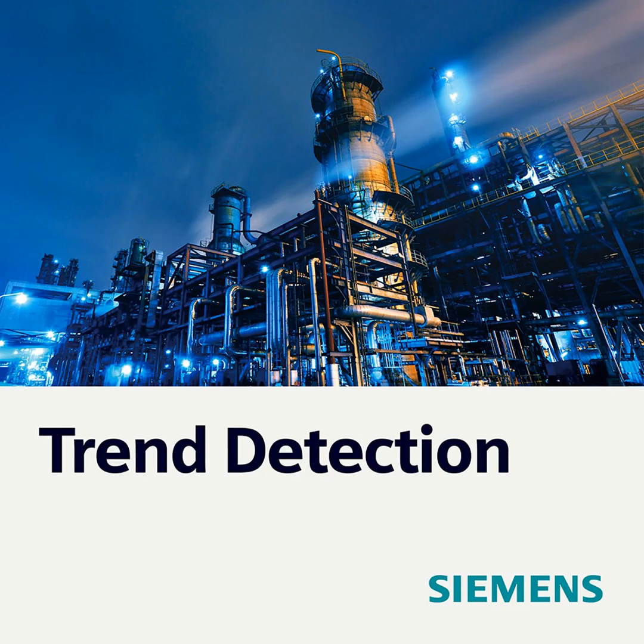With Senseye, you don't really need a data scientist to set up the project or to train a model or something like that. Senseye will do it for you. So when the data is streaming to the Senseye platform, typical condition monitoring data like pressure, current, torque, vibration, but also possibly temperature, also opening and closing times from valves, could be condition indicators for us. And then we can also add a bit of operating context, like what speed is running on this machine, which recipe is currently running on this machine. Is this the ramp up phase, or is the motor starting?